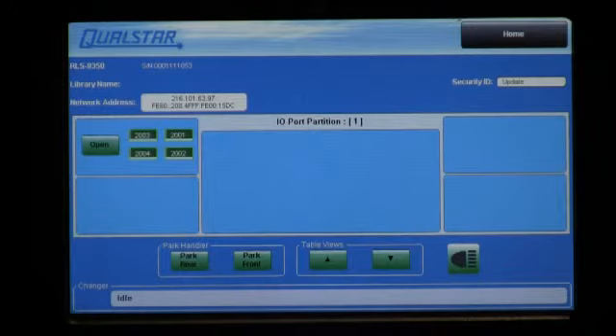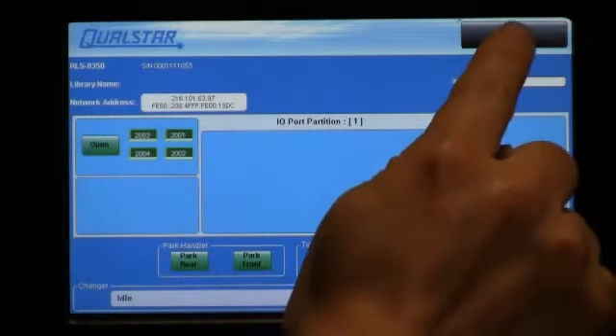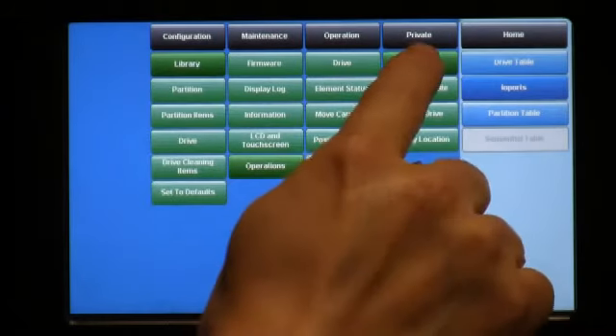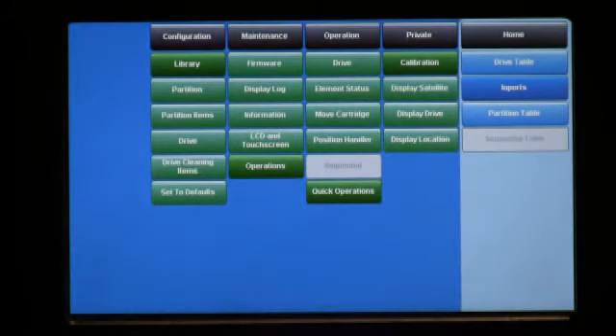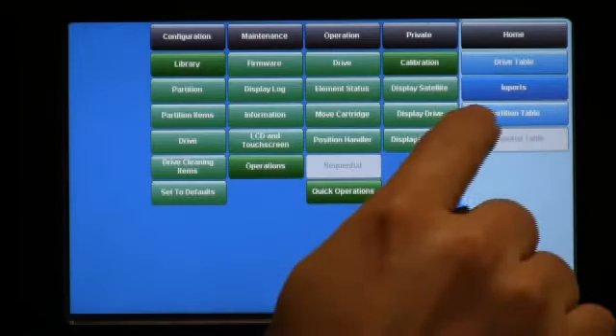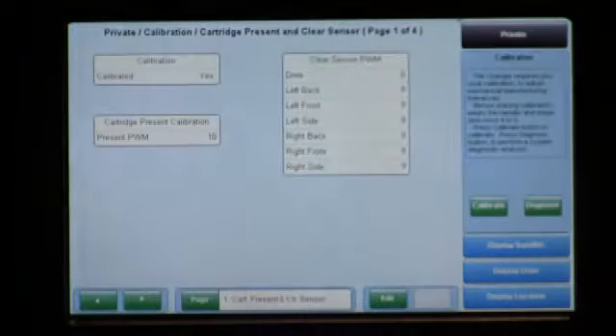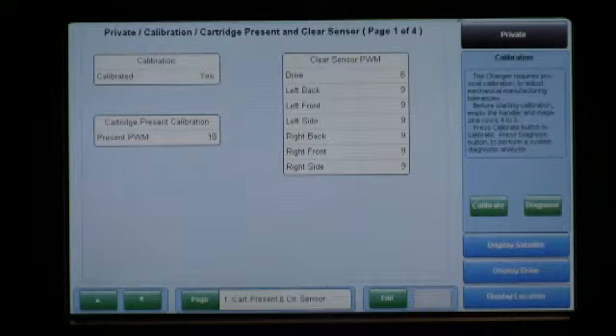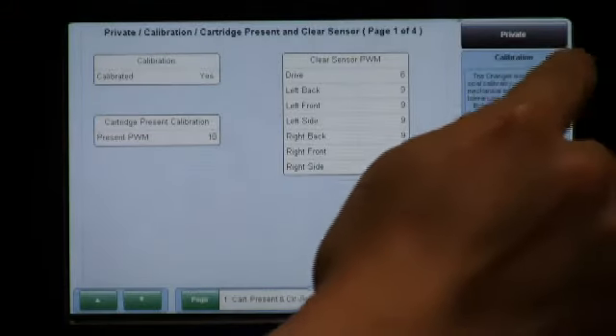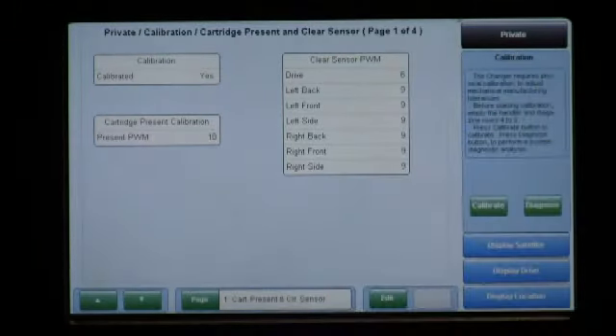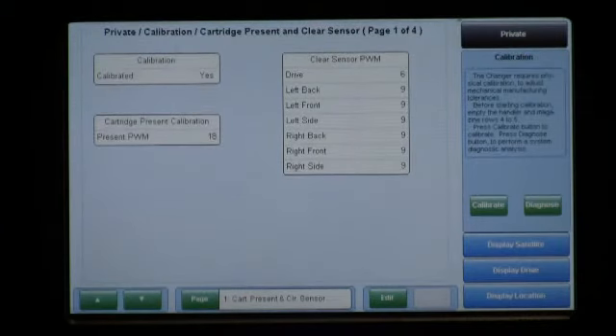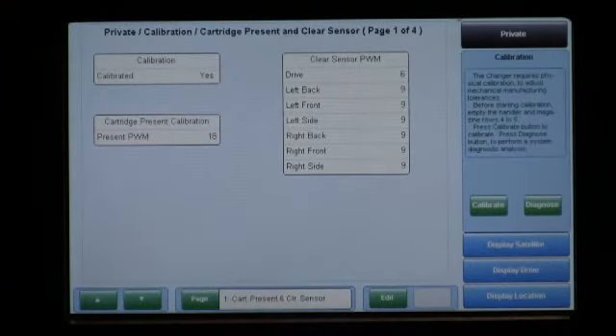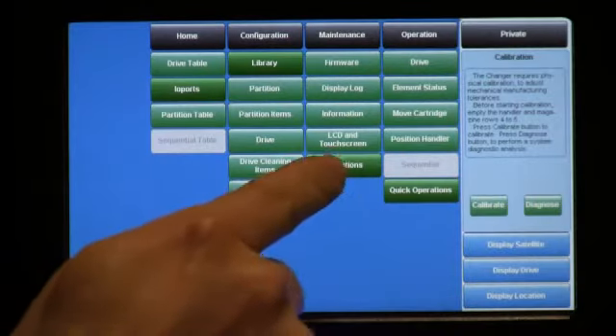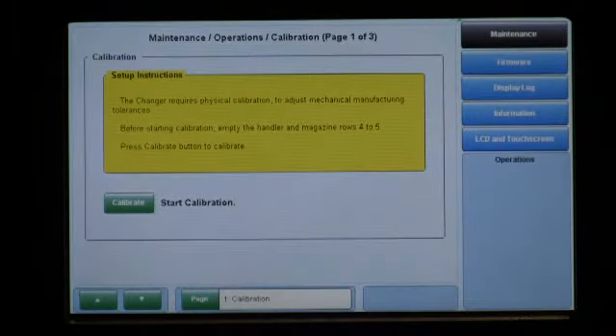Once the security ID has been entered, you can go ahead and press the home button, and you'll notice that there's a column here called private. You can go ahead and select the private calibration button, and that will take you to a new window. If you look at the little message box here, it will tell you what the specific instructions are to proceed with the calibration. Now this message is the same message that you get when you go under the maintenance operations menu.